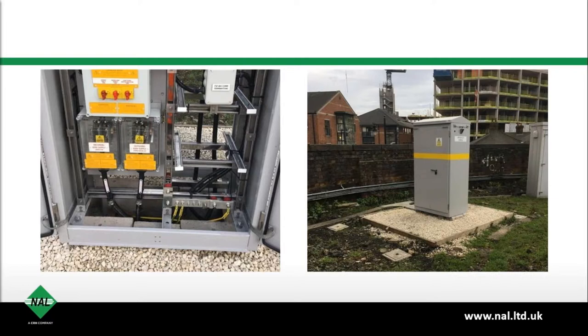So I just wanted to show you a couple of pictures here, to remind you, after seeing that, of all the working space and free access that they had, and how tight and congested it is on the interior face of a cabinet at the moment. That's all the space that you've got to work with, alongside one trough, maybe two troughs, and the hardstand side on the next picture with the external earth pots. And you could definitely walk along that. That's not bad ground to walk on. So it's things like that that we're trying to eradicate.